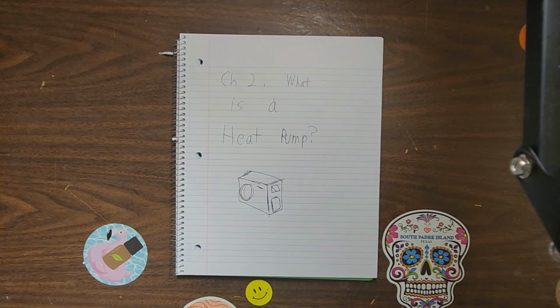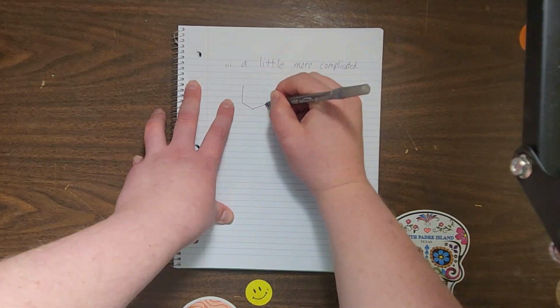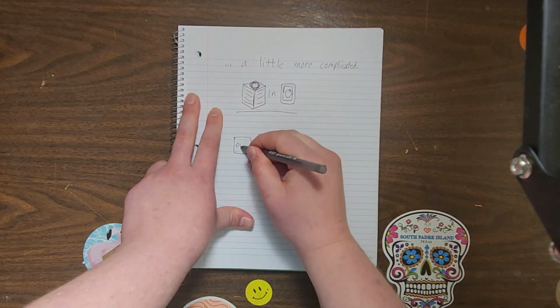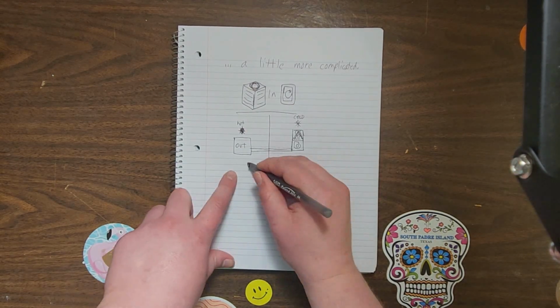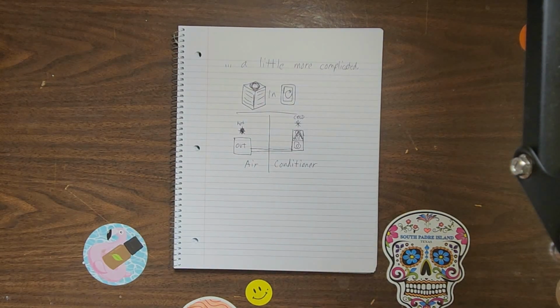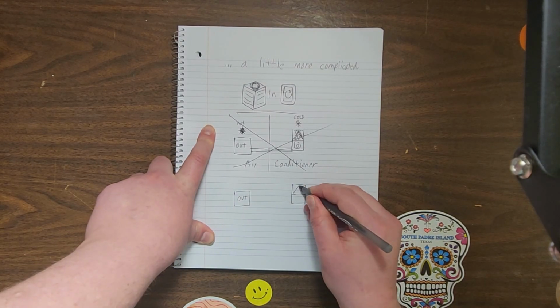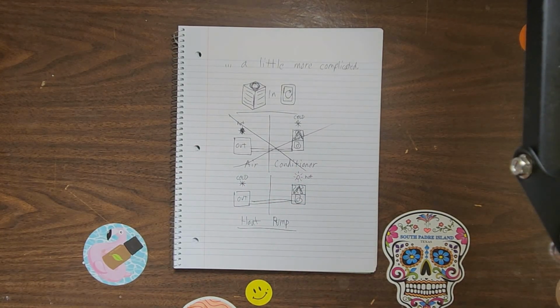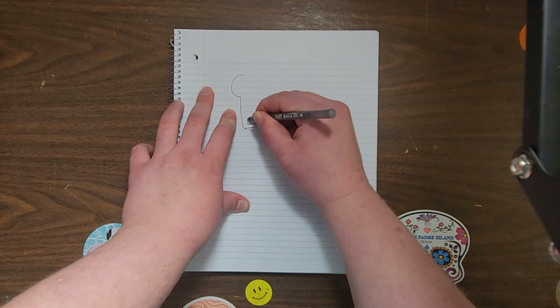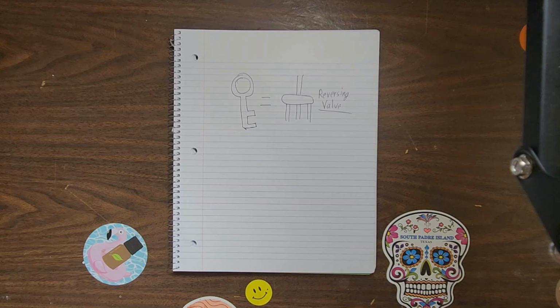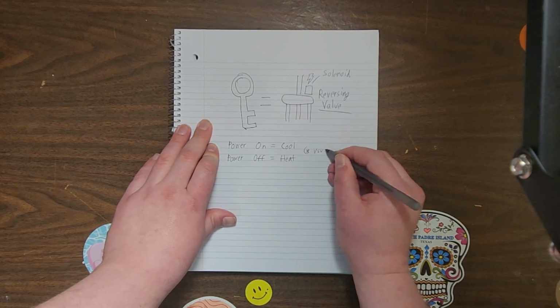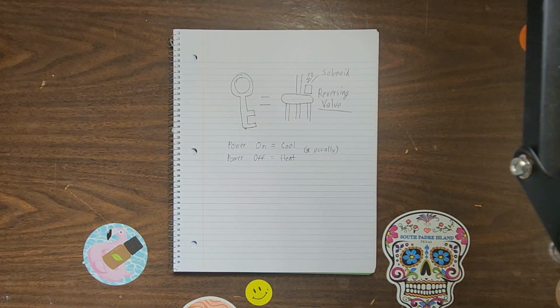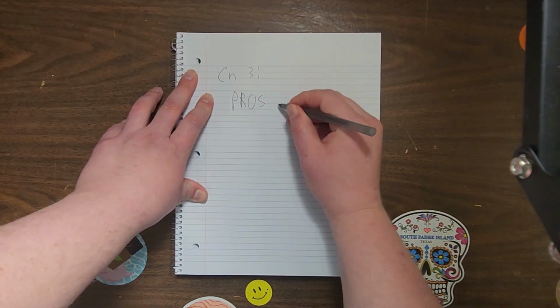This one's a little bit more complicated. In the most basic sense, a heat pump is an air conditioner run in reverse. An air conditioner is designed to absorb heat from inside a space using the indoor coil, called the evaporator, and move it outside to get rid of it using an outdoor coil, called the condenser. A heat pump uses the same cycle, but it's able to run in reverse. So instead, the outdoor coil will try to absorb heat from the outside and get rid of it using the indoor coil. The key to all of this is a component called the reversing valve. The reversing valve contains a sliding valve that can be opened and closed using a solenoid. Depending on if the power is applied to this valve or not, it'll dictate if the unit is in heating or cooling mode. Now, what are the pros and cons of everything?